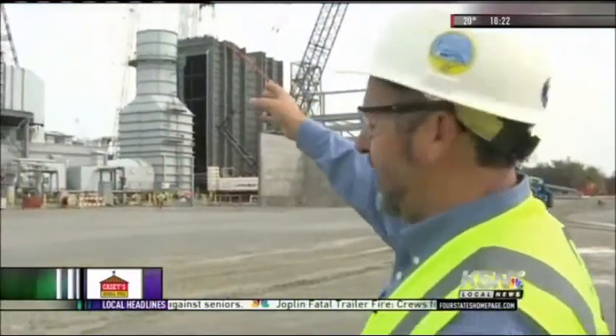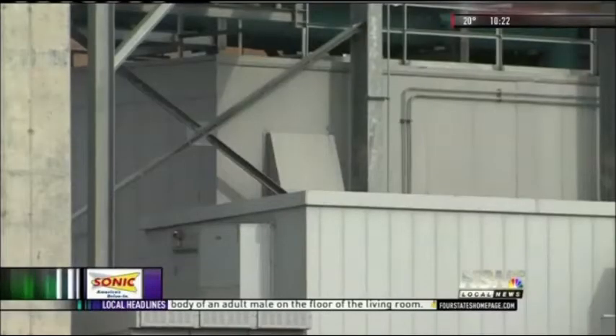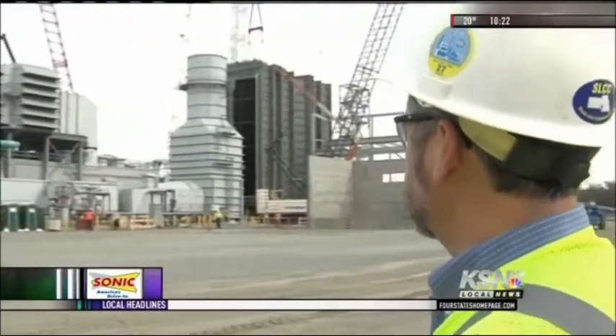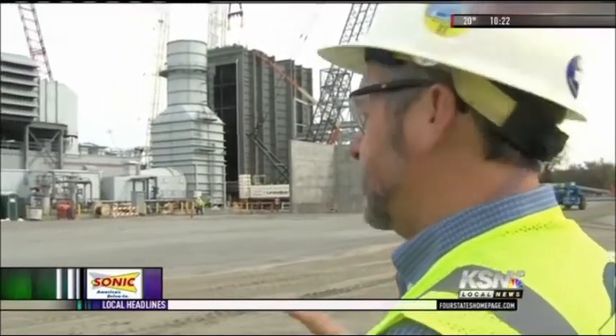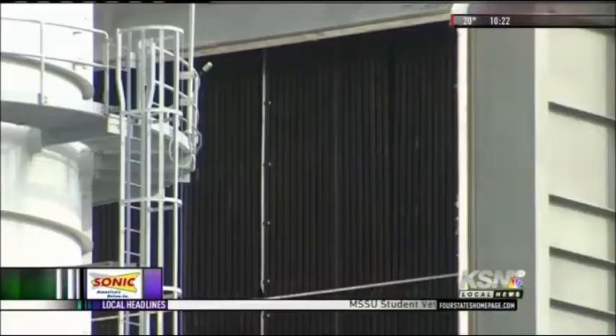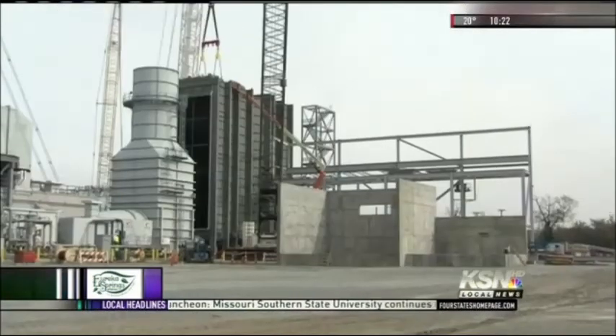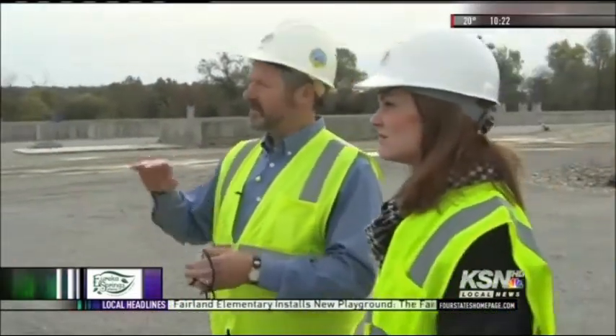We bring in air through the air filter, it goes into the combustion turbine. We bring in gas through our filter, the gas and air mix, it's ignited. It's like a jet engine — the gas expands and it goes through four rows of blades and picks up energy. That exhaust then goes into the stack. The Heat Recovery Steam Generator, or HRSG, captures the heat and superheats the steam. It's like a radiator with fin tubes, and because the exhaust gas is clean, it can absorb the heat a lot better.